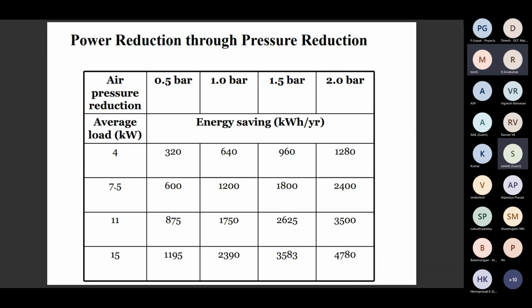Power reduction through pressure reduction. The second thing is the optimized pressure. Now, every 1 bar reduction reduces the energy consumption by 6 to 8%. See here, one table gives average air pressure reductions of 0.5 bar, 1 bar, 1.5 bar. For a 4 kilowatt machine, a 0.5 bar reduction will yield 320 units per year, and a 2 bar reduction will give 1280 units, whereas a 15 kilowatt machine gives nearly 2390 units at the rate of 1 bar, and a 1.5 bar reduction saves nearly 3,580 units.